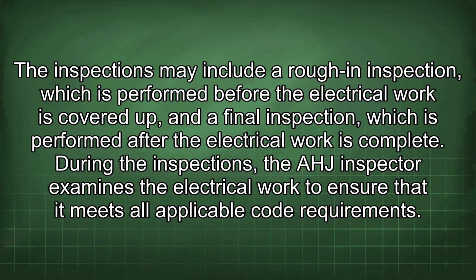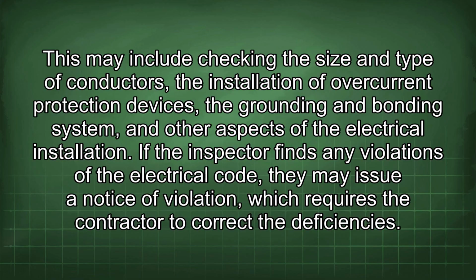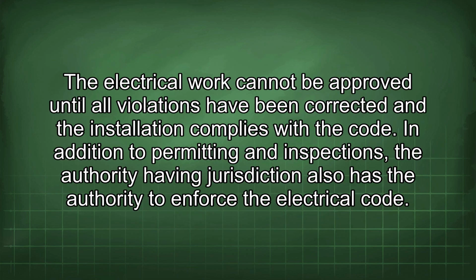The inspections may include a rough-in inspection, which is performed before the electrical work is covered up, and a final inspection, which is performed after the electrical work is complete. During the inspections, the AHJ inspector examines the electrical work to ensure that it meets all applicable code requirements. This may include checking the size and type of conductors, the installation of overcurrent protection devices, the grounding and bonding system, and other aspects of the electrical installation. If the inspector finds any violations of the electrical code, they may issue a notice of violation, which requires the contractor to correct the deficiencies. The electrical work cannot be approved until all violations have been corrected and the installation complies with the code.